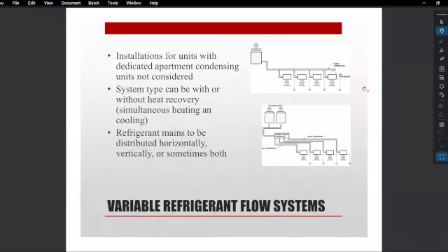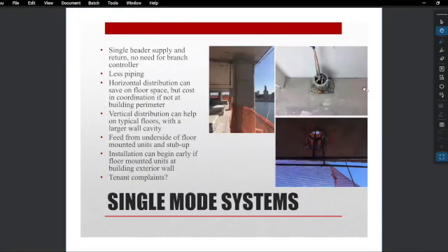Like I said before, VRF systems are ubiquitous in passive house jobs. On all of our passive jobs, the residential heating and cooling is done with variable refrigerant flow systems. And those systems can either be with or without heat recovery. The configurations that we generally consider all involve an air-cooled condensing unit that's serving multiple apartment units. So we don't have any one-to-one ACU to apartment setups. The single mode system, what I mean by that is just the unit is either in heating or cooling.